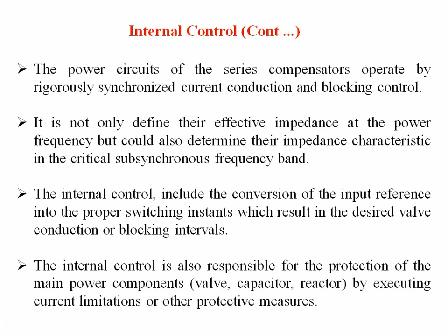So this internal control is also responsible for the protection of main power components, that is valve, capacitor, reactor, by executing the current limitations or other protective measures. Structurally, the internal controls for the three variable impedance type compensators, that is GCSC, TCSC and TSSC, could be similar. But their function is simply to define the conduction and or the blocking intervals of the valve in relation to the fundamental component of the line current.